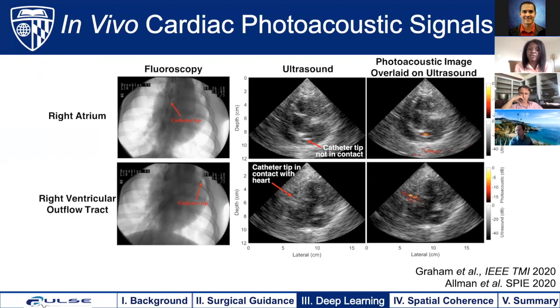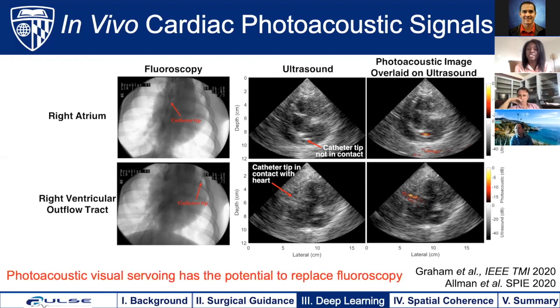So when we insert an optical fiber into the hollow core of the cardiac catheter, as you saw on the previous slide, and we make the photoacoustic images within the beating heart, we get the exciting results shown on the right, telling us that we can see catheter tips in in vivo photoacoustic images regardless of their contact with tissue. And we can see this without requiring ionizing radiation. This result alone implies that we can potentially use photoacoustic imaging to replace fluoroscopy. My vision in particular to replace fluoroscopy is to have the system as unobtrusive as possible. So we want wireless ultrasound probes attached to body-mounted robots, and we would use miniaturized laser systems to deliver this technology. One challenge though with the miniaturized laser systems is that they tend to produce low laser energies.